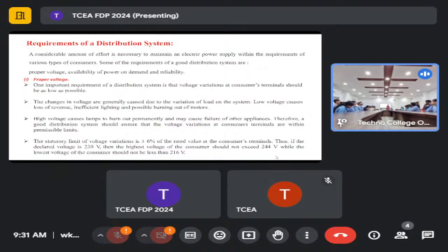Suppose it's a three-phase, four-wire but three-wire motor, 415 volt, plus minus 6%. Now minus 6% means 415 minus 6%, say 380. If the voltage level goes below 380, the motor is designed for 415 plus minus 6%, but when the voltage level goes below 380, the motor will try to maintain its torque. When it tries, it will draw more current from the system, and in the process it will burn.